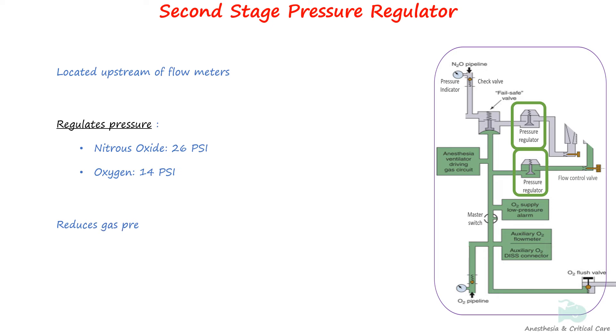Some anesthesia machines have pressure regulators in the intermediate pressure system just upstream of the flow indicators. These regulators reduce pressure further to around 26 psi (177 kPa) for nitrous oxide and 14 psi (95 kPa) for oxygen, ensuring that the pressure of gas supplied to the flow indicators does not fluctuate. The flow through flow meters remains constant when pressure remains constant.